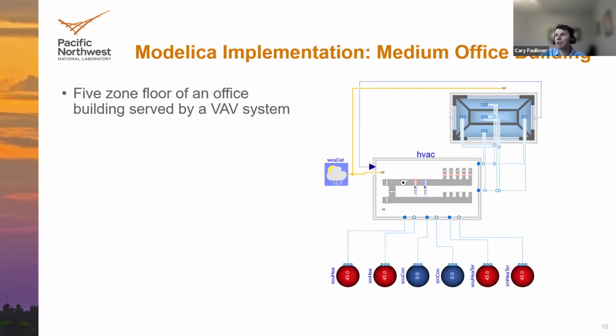So now I'm going to talk about how we model these aspects in Modelica with an example for a VAV system for a medium office building. So starting from the top level, this is what this system model looks like. It's in the Modelica Buildings library. It's a single floor which includes 5 zones of an office building served by a VAV system.